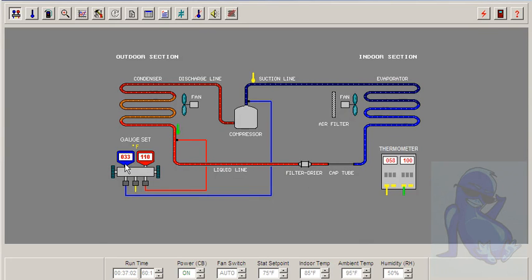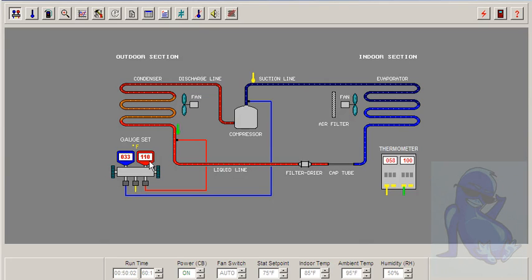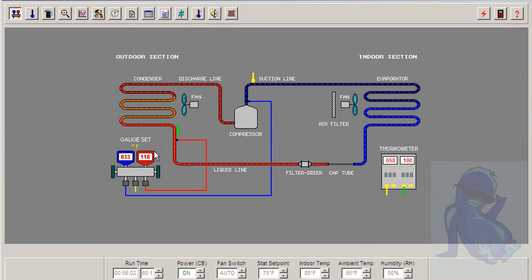You can see our evaporator is changing state at a low 33 degrees. We've got low pressure in our evaporator. The condenser is condensing at 110, which is also low. So we're low on the condenser side, the high side of the system. We're low on the evaporator side.